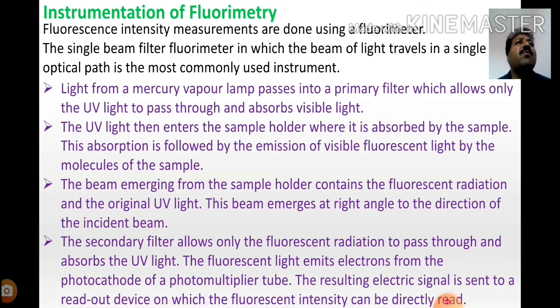The UV light then enters the sample holder, where it is absorbed by the sample, and the absorption is followed by the emission of visible fluorescent light by the molecules of the sample. Then the beam emerging from the sample holder contains the fluorescent radiation and the original UV light. This beam emerges at right angles to the direction of the incident beam. The secondary filter now allows only fluorescent radiation to pass through while it absorbs the UV light.